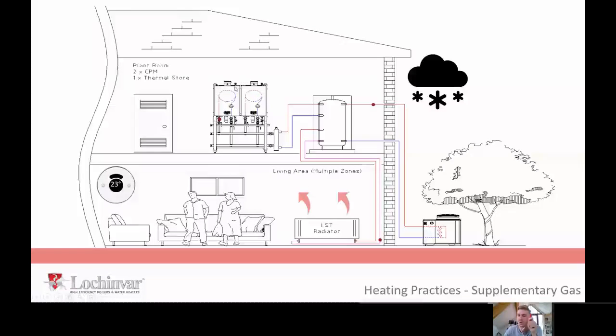You never want to end up with a situation where the gas product dominates the load. You almost want the heat pump in a hybrid style system to be working as like the base load product. And then when the outside air temperature gets beyond 7 degrees for this building, the air source heat pump's never going to turn off. It'll work at 100% rate forever, and the gas boiler is just going to do your extreme peaks and troughs. So that's a hybrid style system.